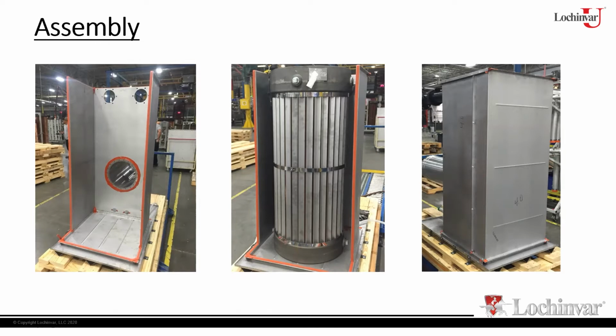Now, once it goes to the line, we're going to add what's called V baffles. And as you can see on the heat exchanger pictured there, these are a series of baffles that fill up between the actual tubes. So there's going to be gaps between the tubes, and we want to put something in there that's going to force those flue gases to go through the path of the fins. If for some reason those baffles weren't there, your flue gases will shoot through the gap, and we're not going to get as good of a heat transfer. Your stack temperatures would increase considerably. The heater would still fire and still operate, but your stack temperatures are going to go up because we're not getting the heat transfer that we should be getting. So the V-baffles serve a pretty good purpose, right? They serve a valuable purpose by filling those gaps up and forcing the flue gases through those paths.